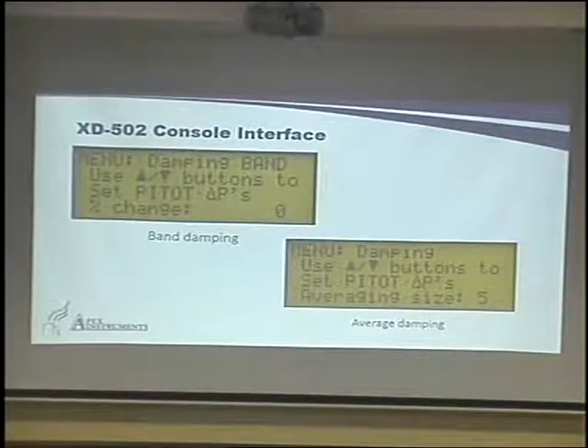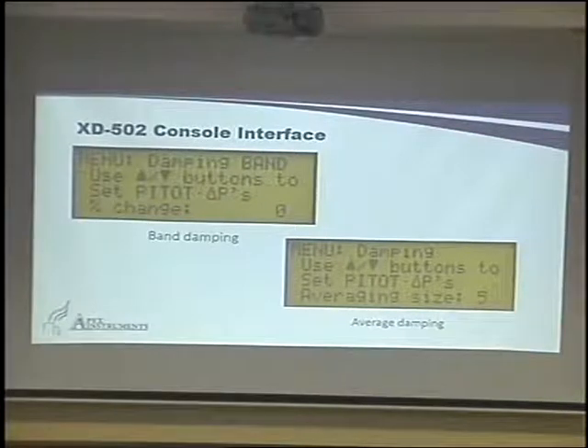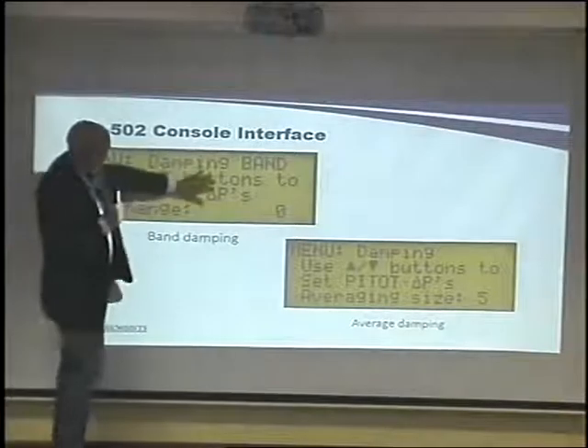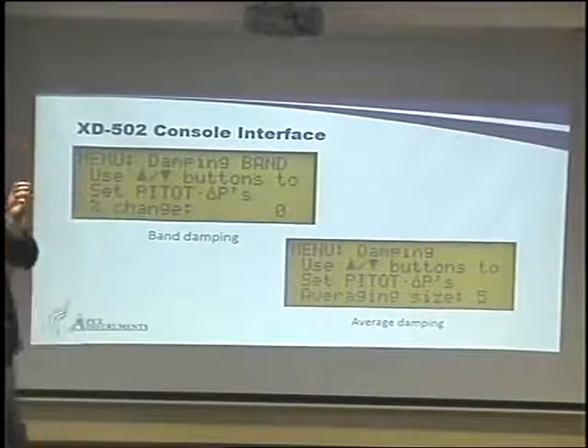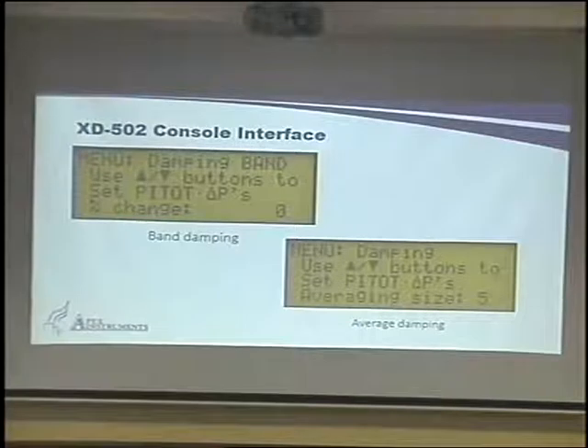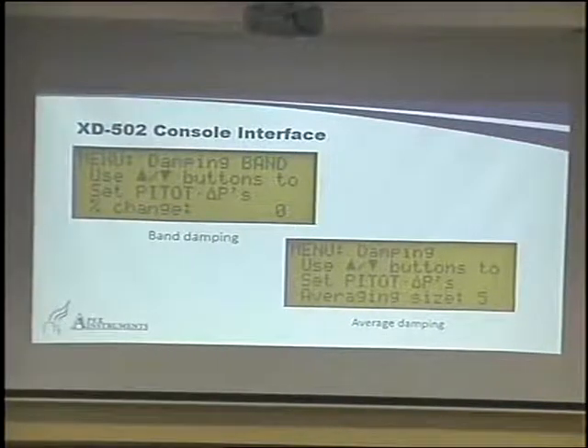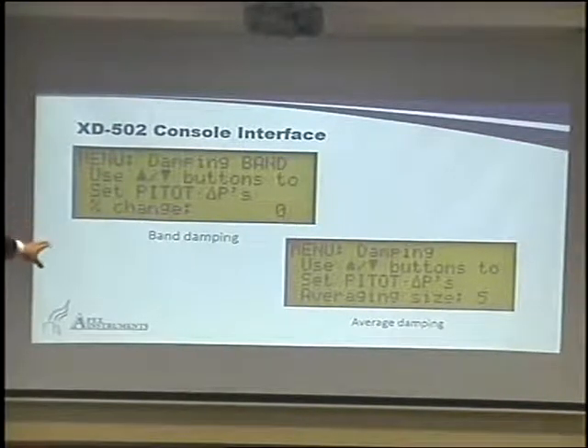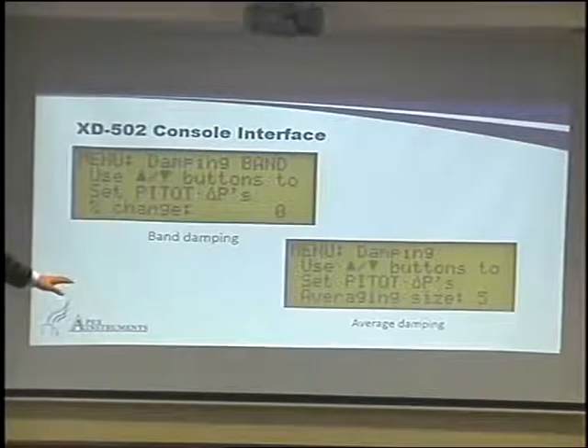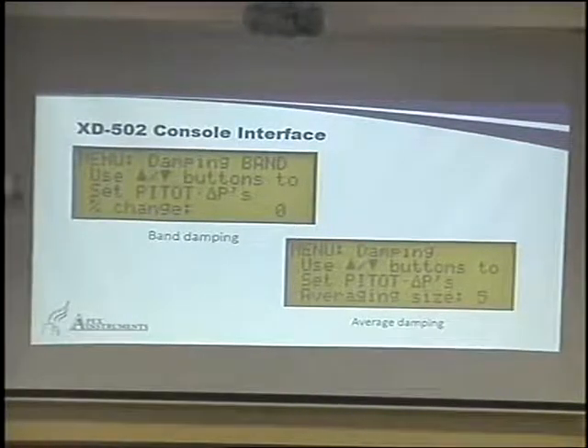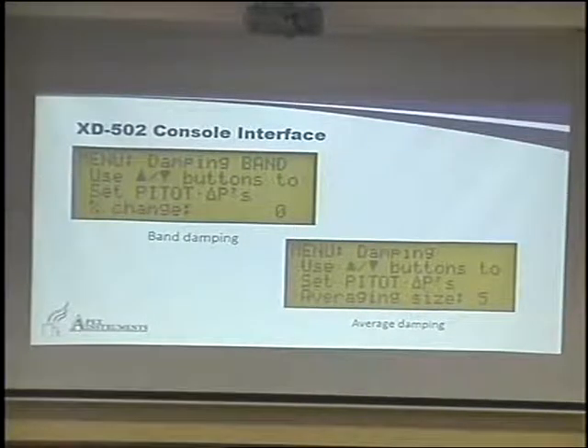By the time that happens, then I make my adjustment, I've been out of isokinetic sampling for well over a minute, okay? I might be sampling high or low, depending on the situation. So what you can do is you can say here that if any value within my average changes more than 5% or 10%, throw away all the old information and start me a new average.